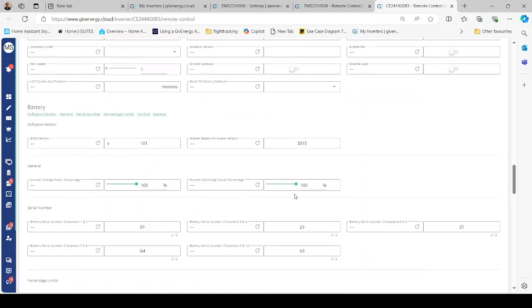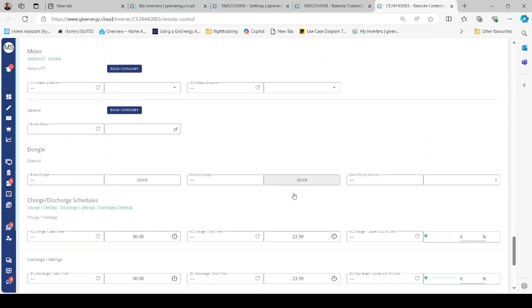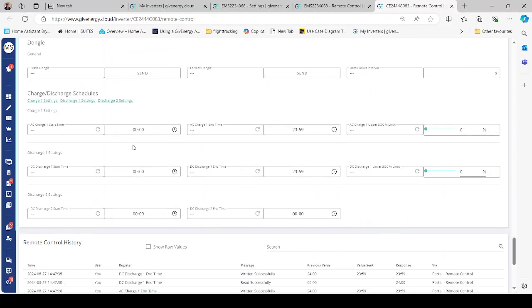And the other most important part to think about here are the charge slots. So they will always be set to 0000 to 2359 for both AC charge start time and DC discharge start time. So if they tell you that one of their inverters is not managing the load, or it is using grid when it's getting up to 3 kilowatts, and you can see that one inverter is not taking charge of that load and supporting it, it is because someone has changed those times. It's very easy to do if on the old app you go and change the times. On the new one you cannot because it's set for EMS only.